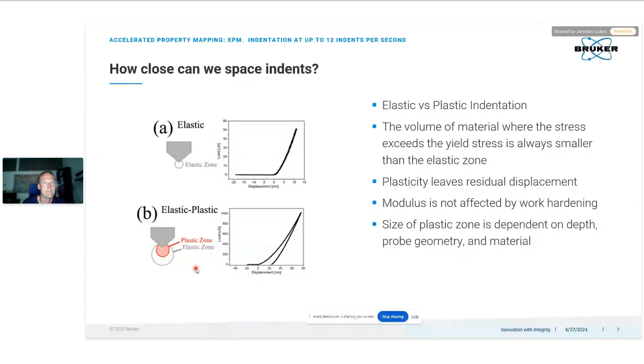That's one thing you have to keep in consideration, and you have to keep the separation large enough to prevent any influence of the neighboring indents, right? The plastic deformation zone should not be part of the plastic deformation zone next to the previous indent. These images describe what I just explained. I would say the deformation zone is a function of tip radius and the material itself. The best way is to make a test, measure the influence, and then decide what the separation should be. Otherwise, there are some rule of thumb values that you can apply for different types of materials.